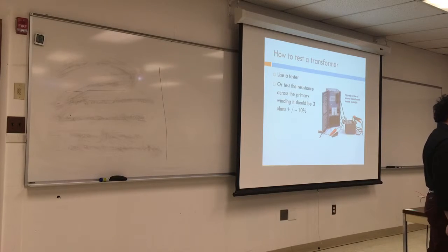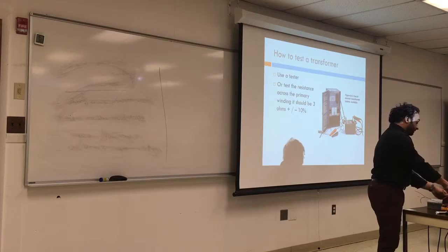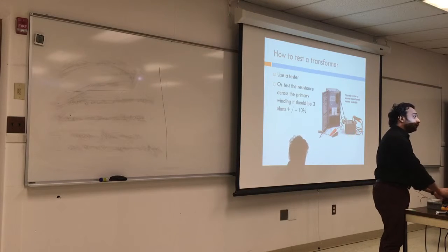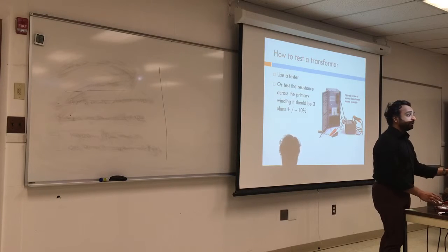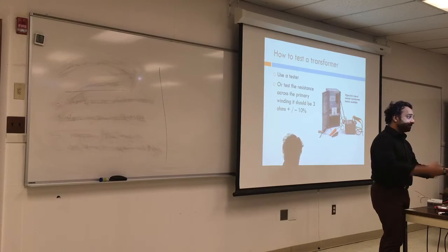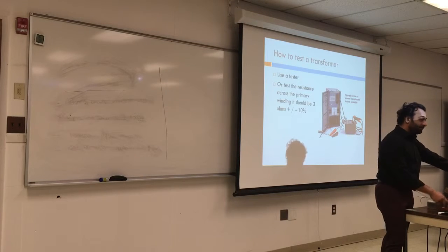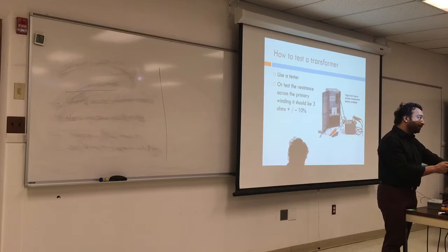Can you use a multimeter? No, I thought you said an amp meter. No, the ammeter is when you turn it on and clip it on one of those leads and watch for the amp to drop. Okay. If it stays constant in 5 minutes, that's good. If you want to test the voltage here, you need a special tool. Never put this into your transformer, it will get fried and probably get zapped.